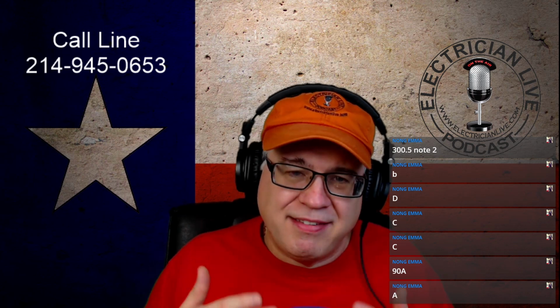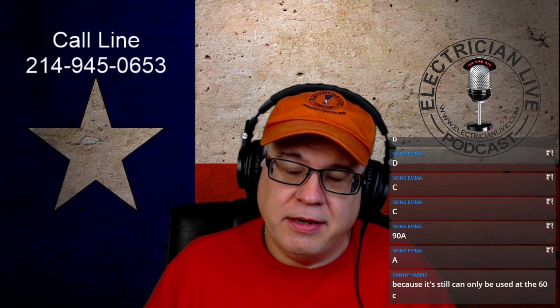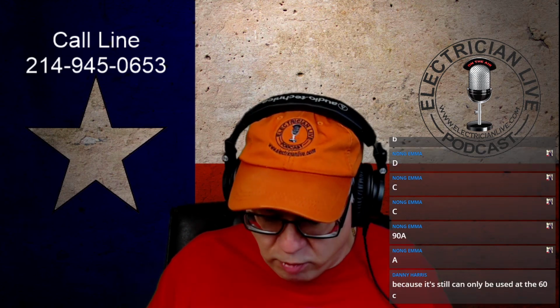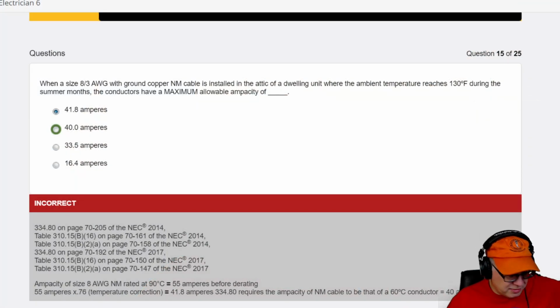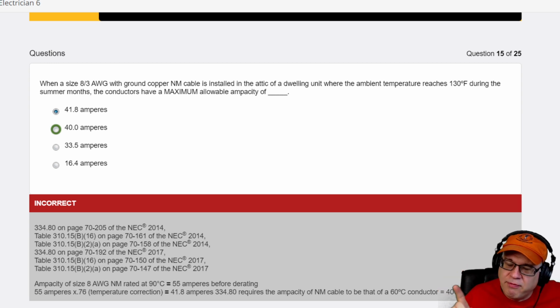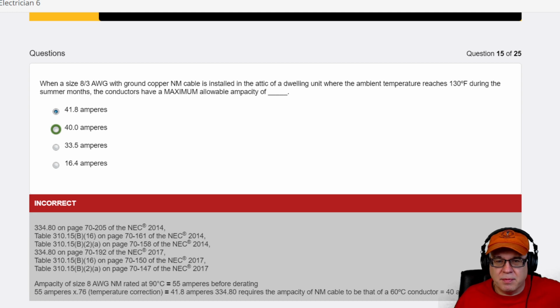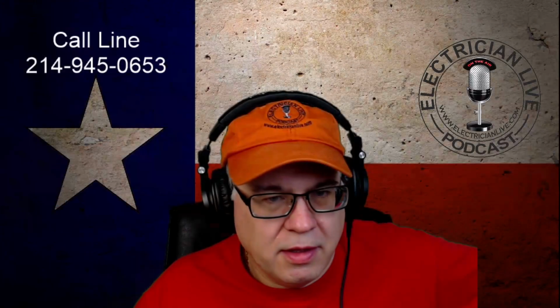But I can start from the 90. Now, why is that important? Because if I had to start from the 60, that conductor would be worth nothing at all. So you see how it works? Okay. Sorry I had to kind of go that route with you. But I did notice that Danny got it. So that was the reason I went through that little thing, because at the end of the day, the 60-degree column still limited at the 40. All we did was go to the 90 to make sure that after we apply that heat, is it still good for the use? Now, what if that value had to come in under 40? Okay, then we have a problem. Then we have a new ampacity value that we have to work out.